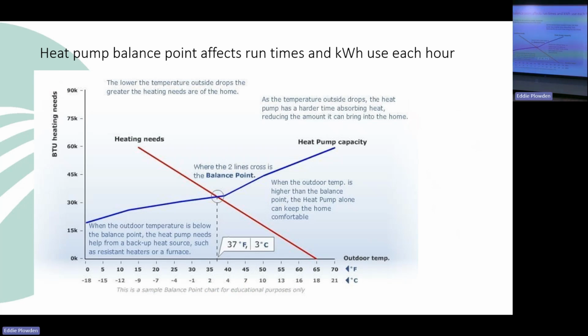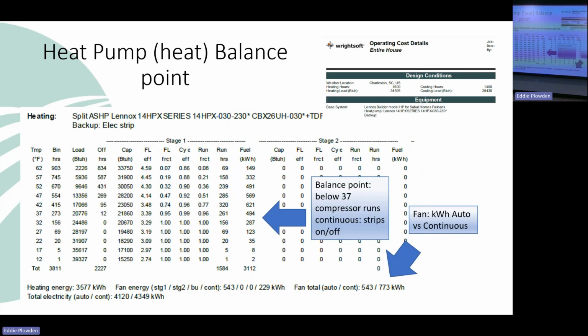And as it gets colder outside in the 40s, the balance point for a heat pump is just when it gets so cold outside that the compressor is running all the time, and it needs a little bit of backup heat from the electric resistive heat to maintain the temperature in the house. And that's what we call a balance point, and that's when the bills do jump up, during that time period. Things can drive that even higher, like a thermostat setting. If a member sets it too warm in the wintertime, it'll cause the unit to run a whole lot more and have a whole lot higher bill. If the unit's not working like it's supposed to, it's going to be a higher bill.